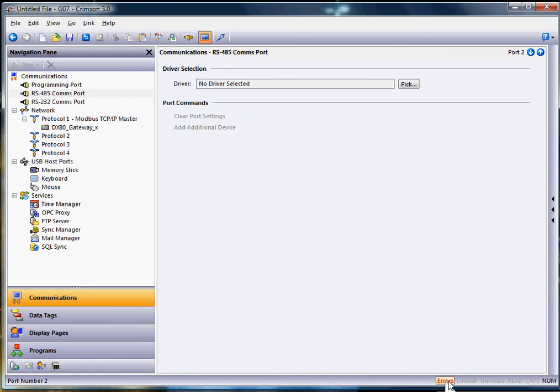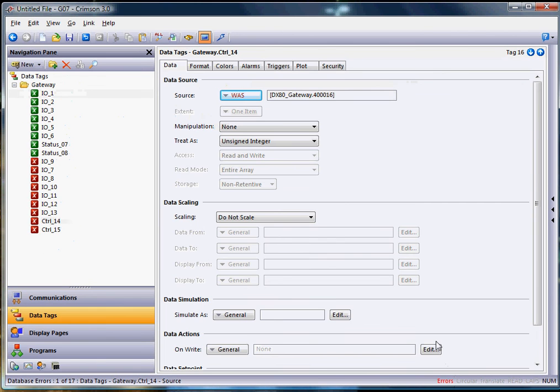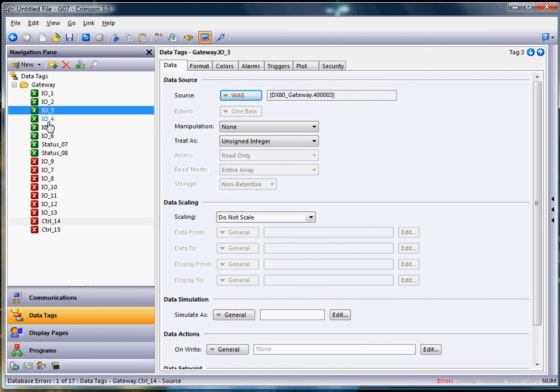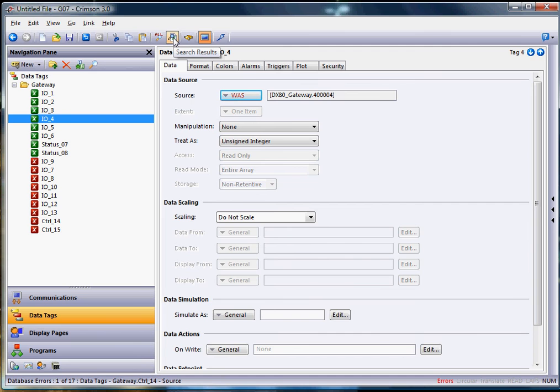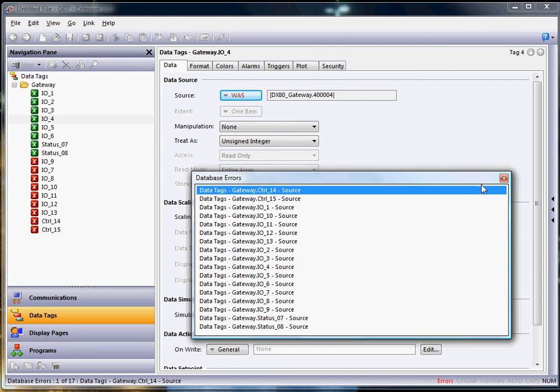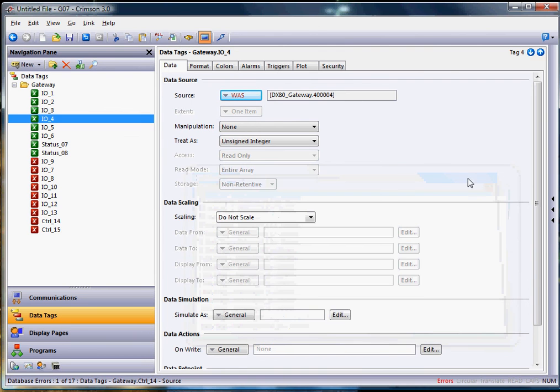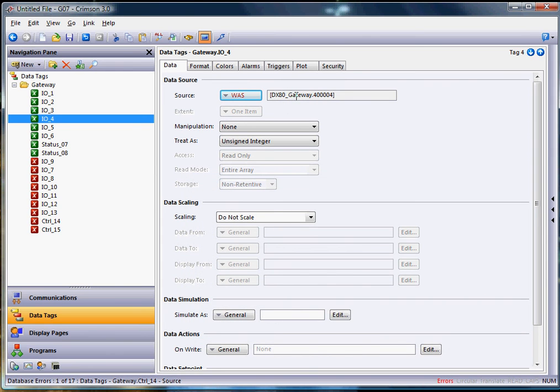You can see right down here it actually brings up the errors. So if I take my mouse down here to errors and double click on this, it actually takes me where the errors are listed. If you ever want to see a listing of the errors, you can always hit this little button right here, search results. That will bring up a table of each individual one that's causing the error. The problem here is that the tag was linked to DX80 gateway device, but we've deleted that.